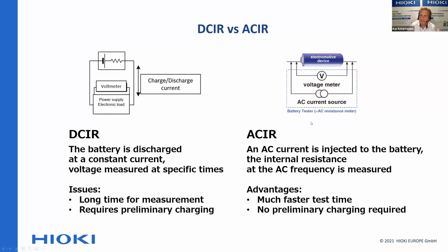It's a 4-wire measurement, with an AC current injected into the battery. At 1 kilohertz, this AC current doesn't have any impact on charge or discharge, because that frequency is too fast to affect the battery's charge or discharge. That's one reason why 1 kilohertz is the safe choice and has been established over the years as the standard.